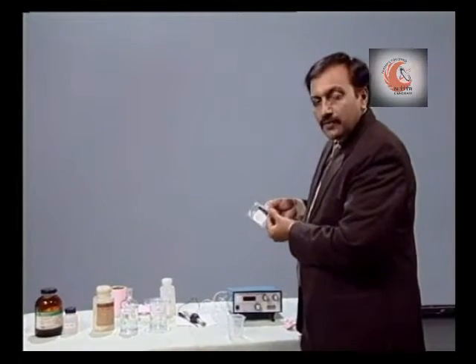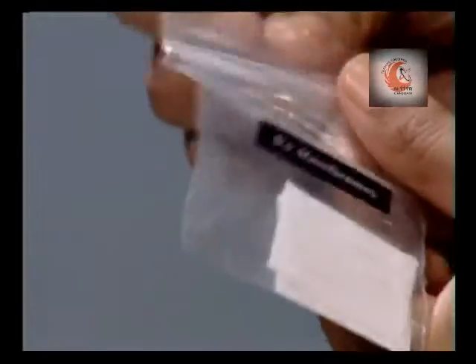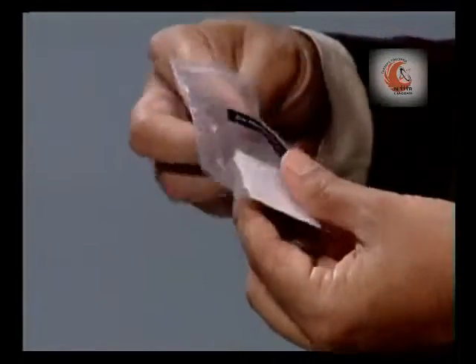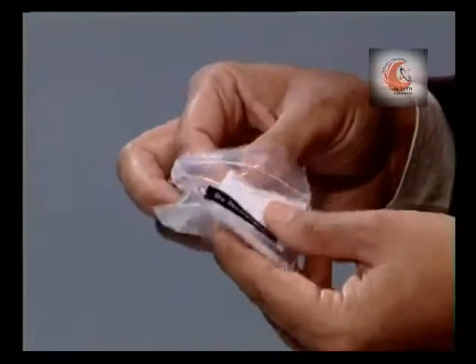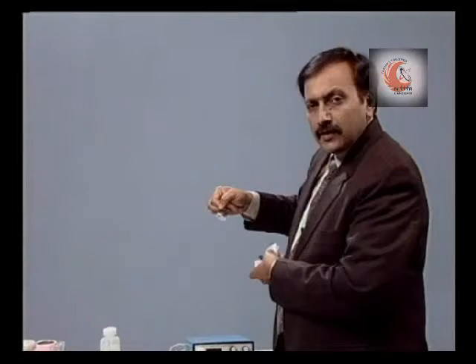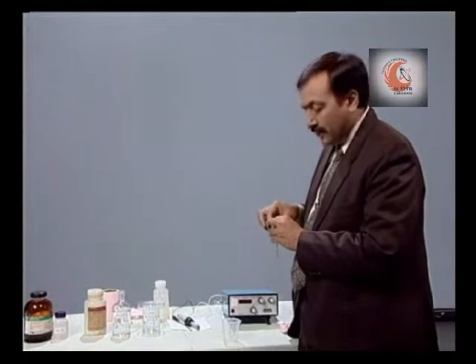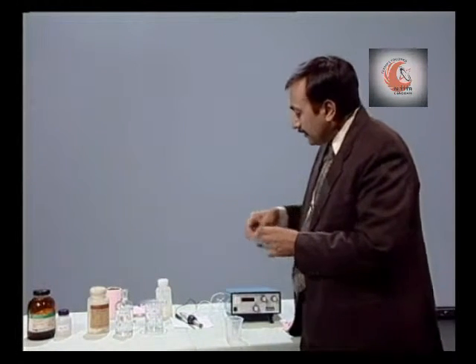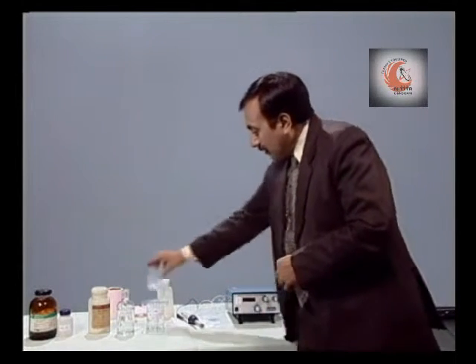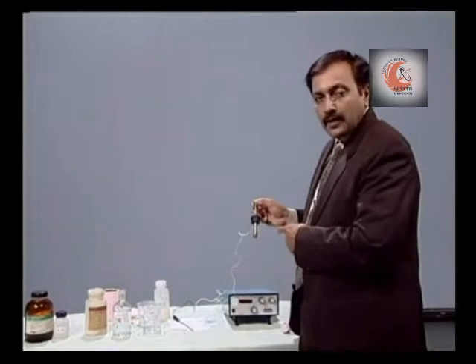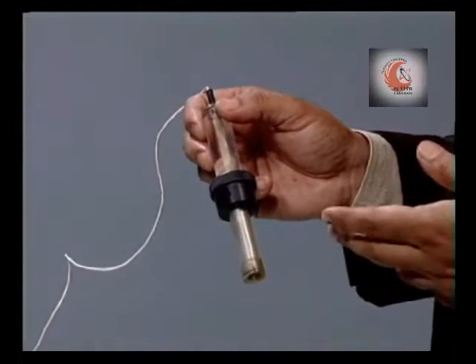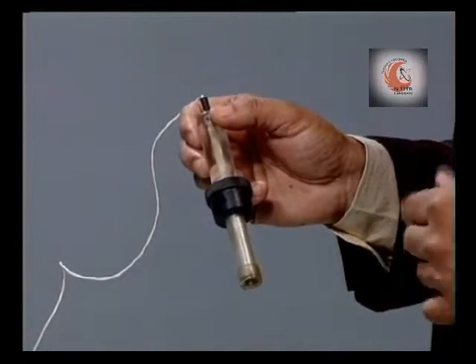A new membrane, if it is to be used, has to be activated first, so that it easily diffuses the current. To activate the membrane, put it in cold water for 2 to 3 minutes and then in hot water for 2 to 3 minutes, and repeat the cycle, and the membrane will be ready for use. Or alternatively, you can put the membrane on the electrode, keep it on for 2 hours and repeat the hot water and cold water cycles twice.